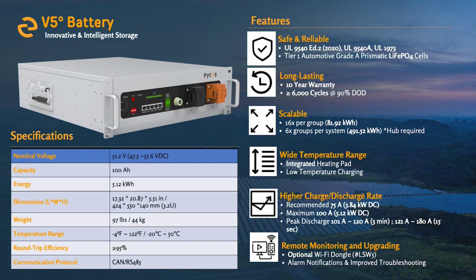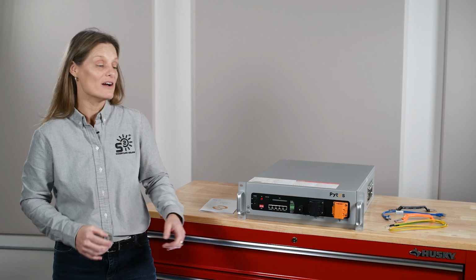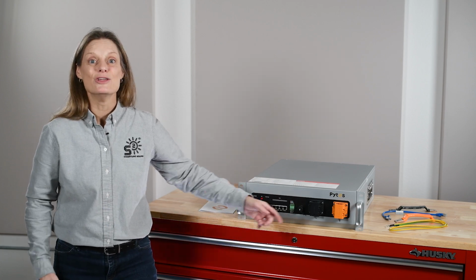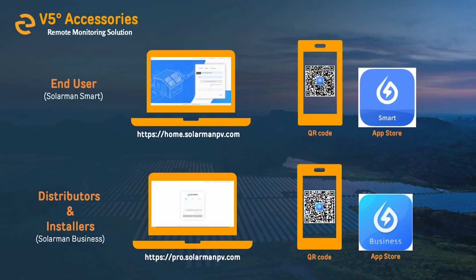As for specs, the V5 has a nominal voltage of 51.2 volts, weighs approximately 97 pounds, and supports a continuous charge-discharge rate of 75 amps with a maximum of 100 amps and peak discharge rates of up to 180 amps for short bursts. With the optional Wi-Fi dongle that you put right here, users gain access to remote monitoring, alarm notifications, and troubleshooting through the SolarMan platform, making management simple and accessible.